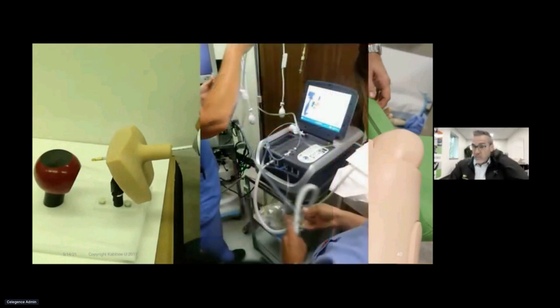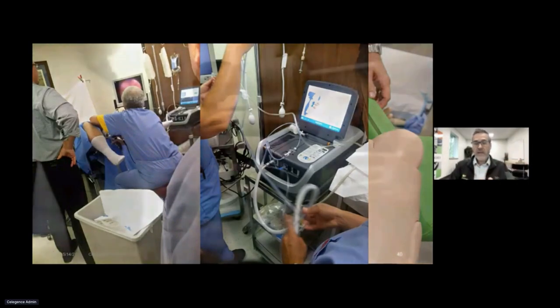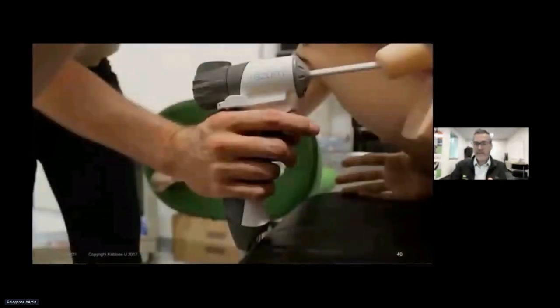And then we go into real use scenarios where now we can go into cadaver labs with users, you can go into animal labs with users, and we do actual setup with actual users, actual technicians, and we log these as actual formative studies where we've got a protocol, we've got data collected, and we've got a report that gives us some of our usability that will all lead to those user interface requirements that come out of that.